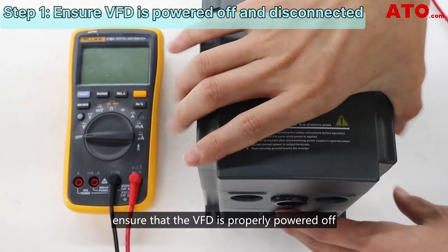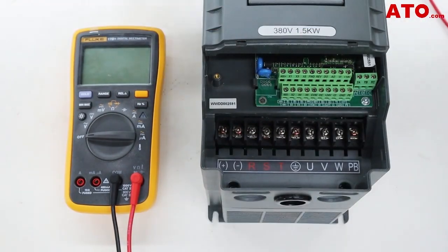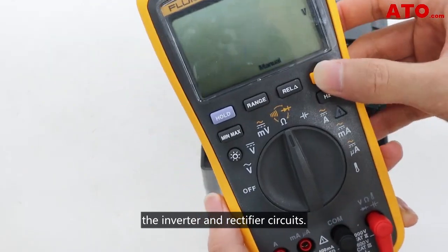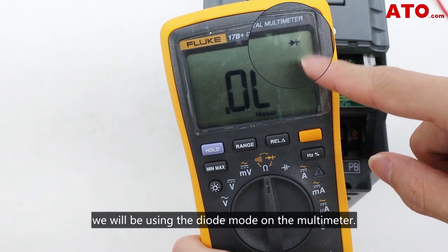Before beginning any troubleshooting, ensure that the VFD is properly powered off and disconnected from the power source. To determine if the VFD can be powered on, we can use a multimeter to check the integrity of the inverter and rectifier circuits. For all the measurements in this test, we'll be using the diode mode on the multimeter.